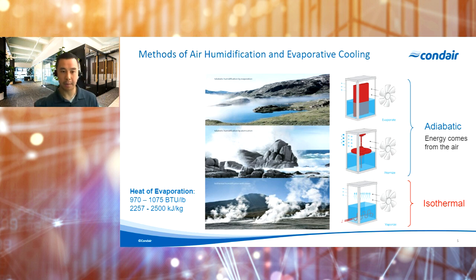If we look at an adiabatic process, we are relying on the energy from the air to drive that phase change. This can be done a couple of different ways. The first is by atomizing the water, or spraying the water into an airstream, where those droplets are then evaporated. The other way this can be done adiabatically is by passing warm, dry air through an evaporative media where the water is evaporated off of it, and we get cool humidified air on the discharge side. In comparison, an isothermal process is where we're putting energy into the system to drive that phase change, essentially boiling the water and creating steam, which is absorbed into the air, increasing the humidity or moisture content.